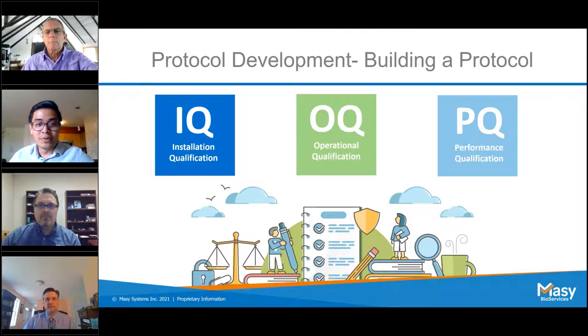In regards to the OQ, it's also important to run air detector tests or Bowie-Dick tests, especially if you're running vacuum cycles, as this is to evaluate and verify the performance of your pre-vacuum autoclave and make sure that it can provide adequate air removal before you run any of your cycles.